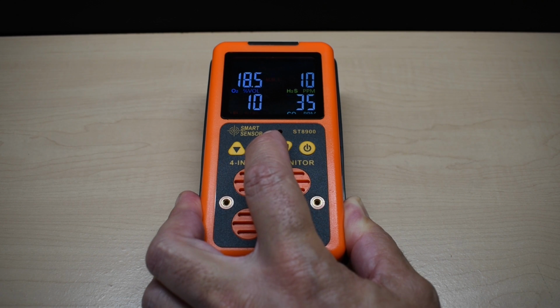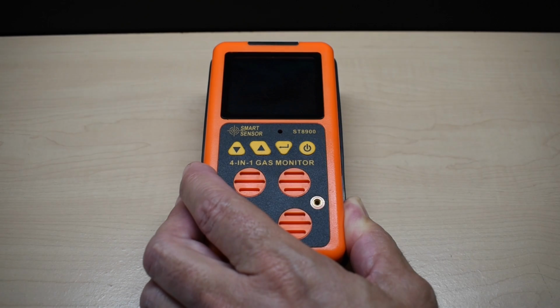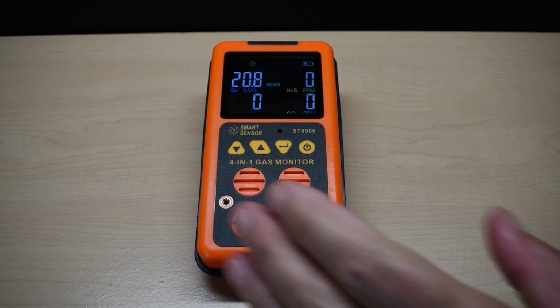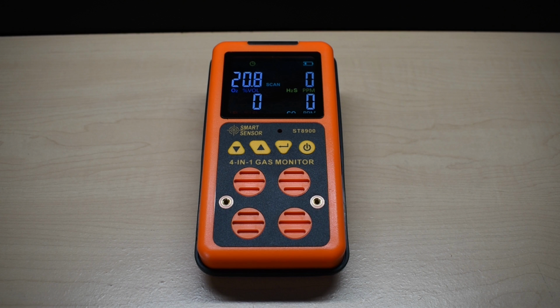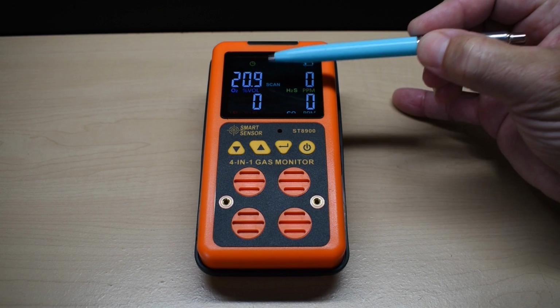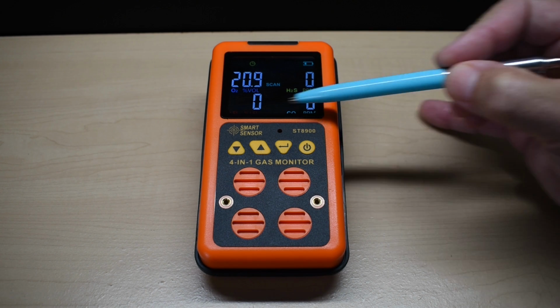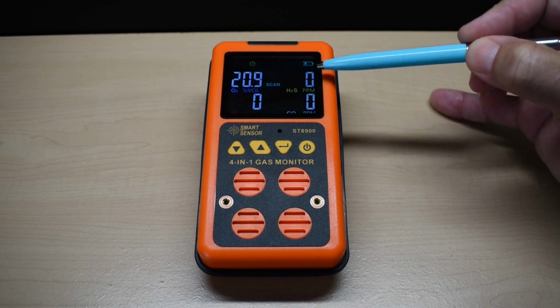All right, and now we're back to these settings. Push this button once, and it brings you back to the main screen. Now let me show you what to do if you get this unit and notice that the oxygen is not calibrated properly, or if these zeros are not set at 0.